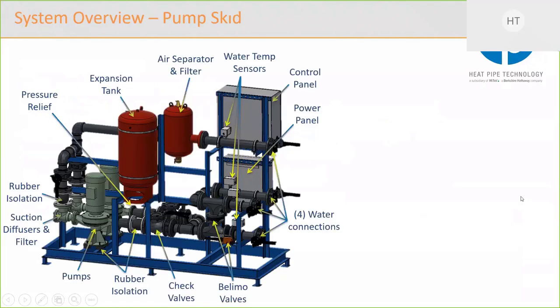This is an example of what a pump skid looks like. On the left, you can see there are two pumps. The big red vessel is the expansion tank. The smaller red vessel is the air separator. And you see there are two electrical enclosures. The upper enclosure is for the control panel, and the lower enclosure is the power panel and the VFDs.